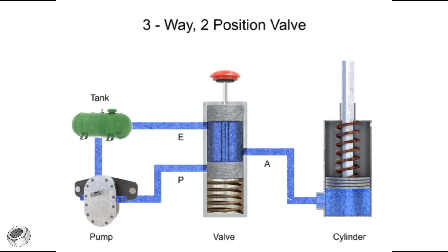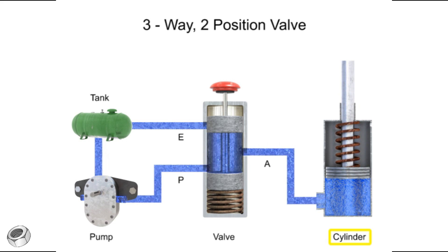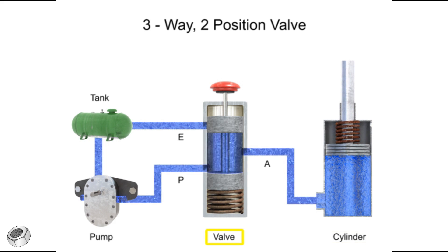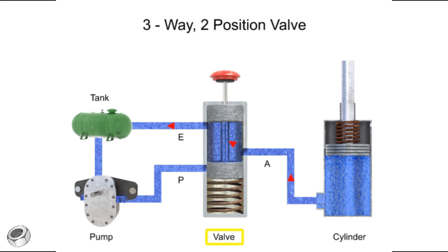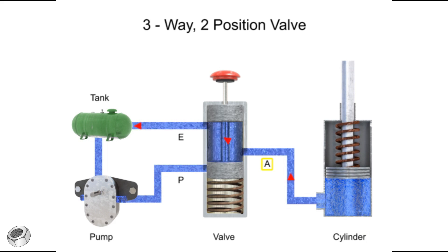Three-way directional control valves have many applications in fluid systems. One of the most common is the control of single-acting cylinders. In this application, fluid is pumped from a tank to pressure port P. With the valve in the normal position, fluid is blocked. When the valve is actuated, fluid flows from pressure port P through outlet port A to the cylinder, which extends and remains extended until the valve changes positions. When the valve de-energizes, the spool returns to position one, pressure port P is blocked, exhaust port E is opened, and the cylinder retracts — fluid flows from the cylinder through port A and out exhaust port E, returning to the tank.